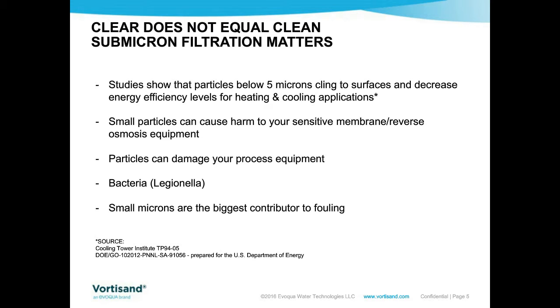Particles can also damage your equipment, either by erosion, corrosion, or blockage. There's also bacteria to think about. Not only do they pose a health risk, such as Legionella, but also they can promote corrosion, like sulfate-reducing bacteria. So small micron particles are the biggest contributor to fouling, and sometimes they should be addressed first.